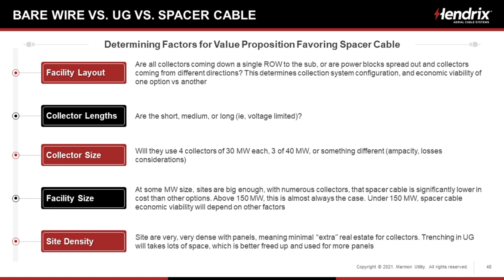And again, I've talked about bare wire versus underground versus spacer cable at a wind or solar or other type of renewable facility, and it's going to depend on a couple of factors. The facility layout: are all collectors coming down a single right of way to the sub, or are they spread out in a star? Do I have 50 on the right, 50 on the left, 50 below, and 50 below left? I might have four lines coming in. I may not have a value proposition for spacer cable. It might be bare wire or underground.